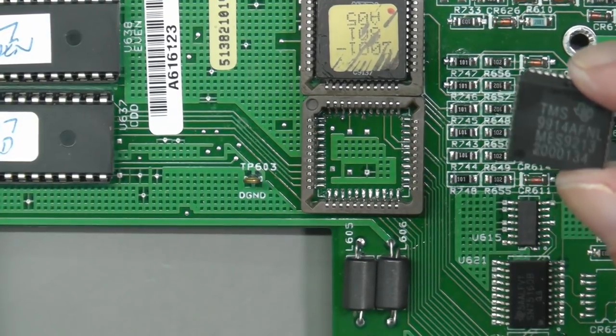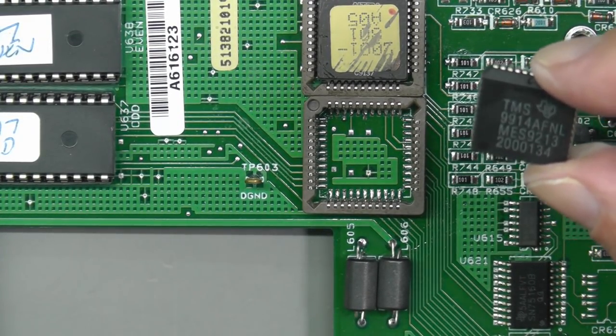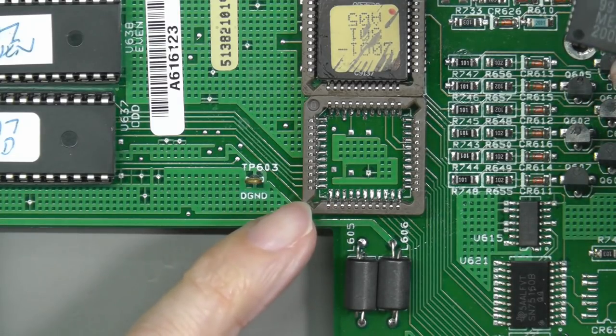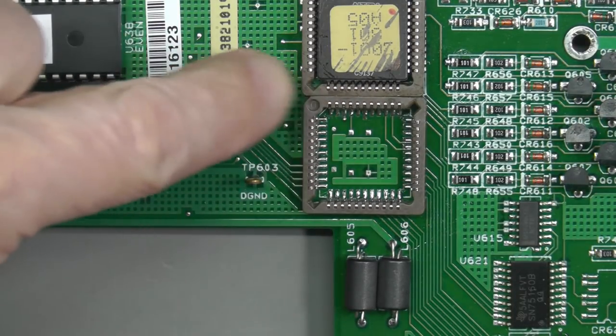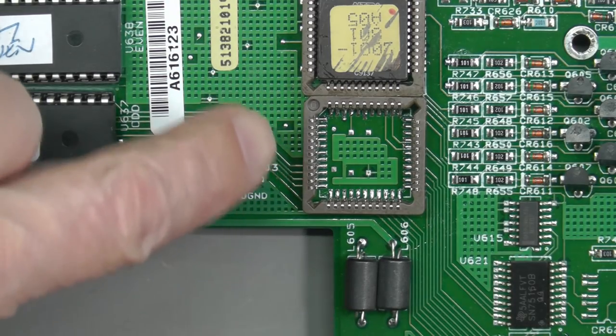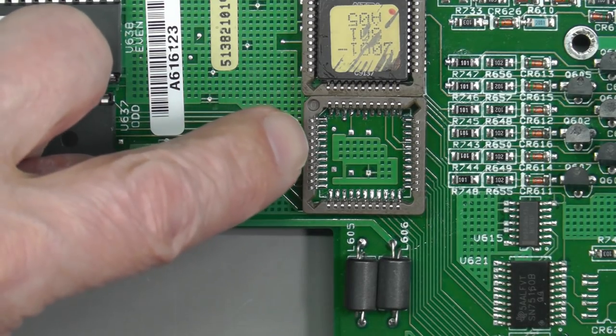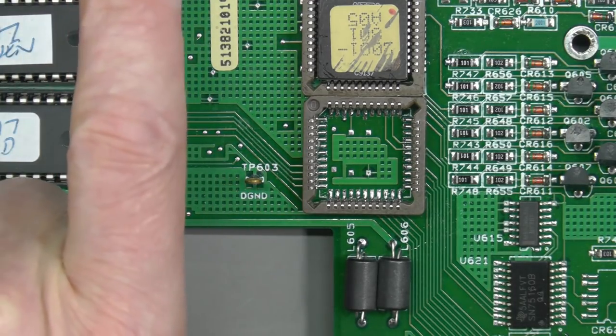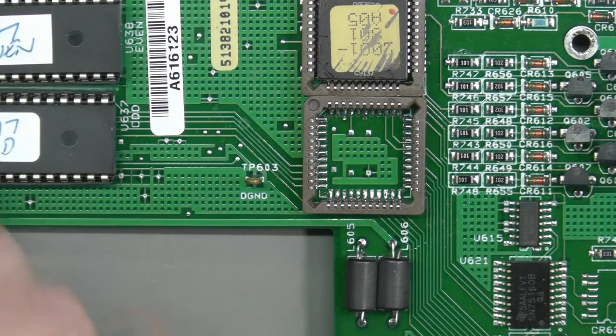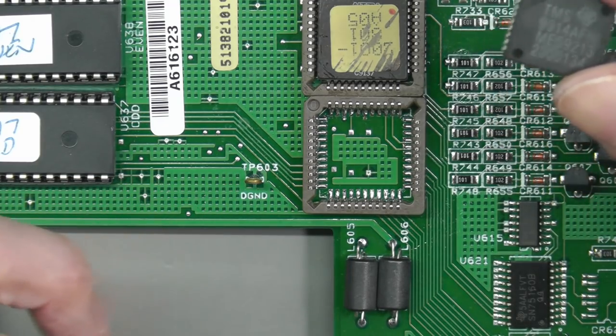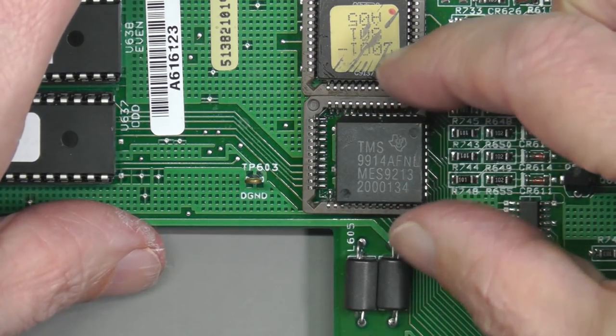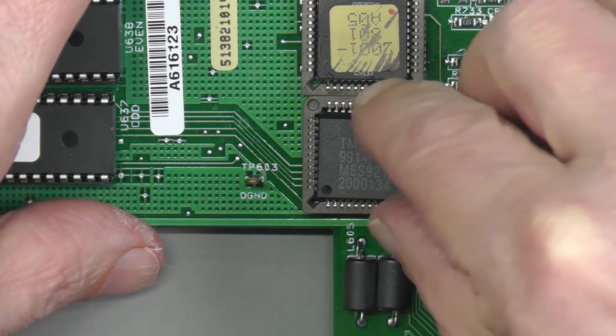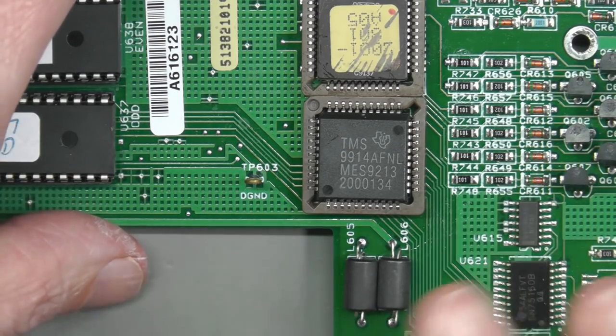Now of course it could be the buffer ICs here or it could actually be the GPIB controller. So I think what I'll do is I'll try replacing the controller first. Well, that's the GPIB controller IC removed from the donor board and I fitted a socket to my digital board here. I had to file down the side of the socket just for the tiniest of fractions, not even half a pad of the IC, just to move the socket very slightly. I've done that and it's soldered up in place. I've got the new controller chip which I can go ahead and fit now.